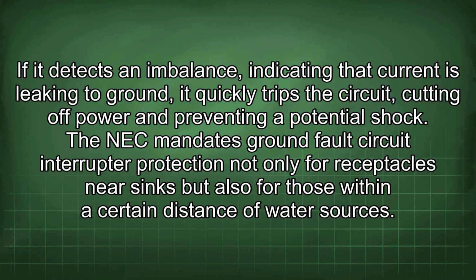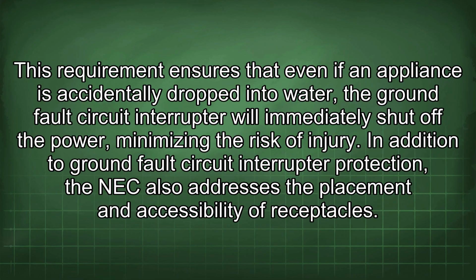The NEC mandates ground fault circuit interrupter protection not only for receptacles near sinks but also for those within a certain distance of water sources. This requirement ensures that even if an appliance is accidentally dropped into water, the ground fault circuit interrupter will immediately shut off the power, minimizing the risk of injury.